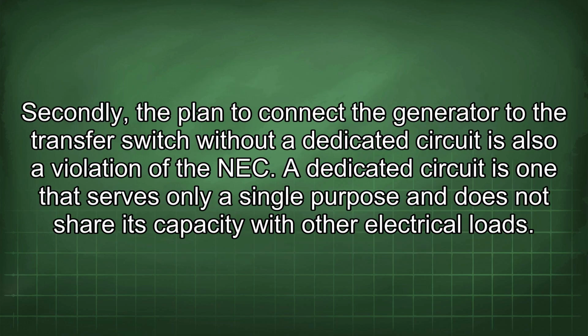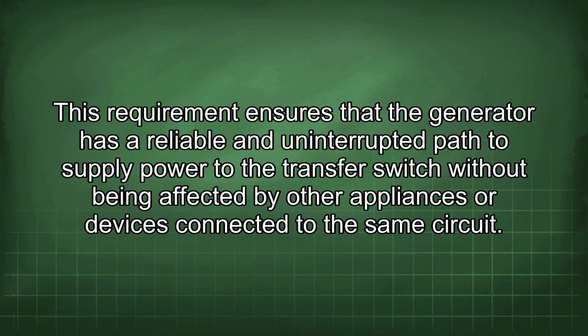Secondly, the plan to connect the generator to the transfer switch without a dedicated circuit is also a violation of the NEC. A dedicated circuit is one that serves only a single purpose and does not share its capacity with other electrical loads. This requirement ensures that the generator has a reliable and uninterrupted path to supply power to the transfer switch without being affected by other appliances or devices connected to the same circuit.